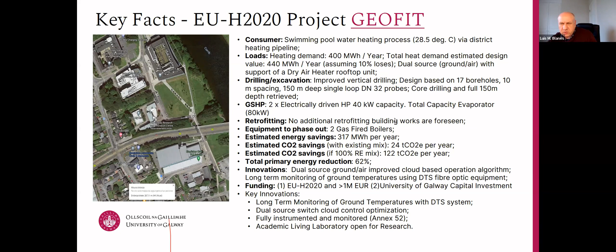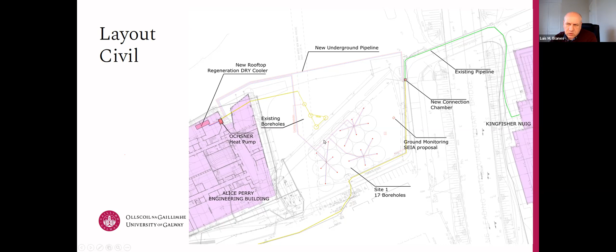Okay, so the layout that you have seen is quite fast. So the drilling field, so the ground source heat exchange is this one. So these are the 17 boreholes. Then there is the manifold. This is connecting to the plant room in the Alice Perry, and this building on the right side is the swimming pool, and this green line here is the existing pipeline that turns in. And we are doing this, the new underground pipeline, a connection chamber, and then the connection to the boreholes.